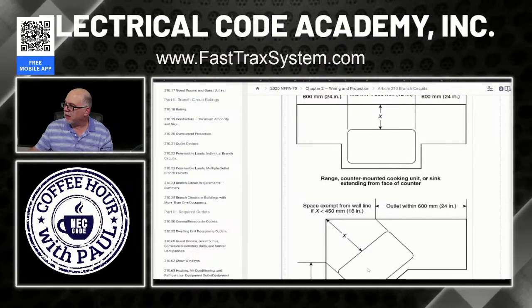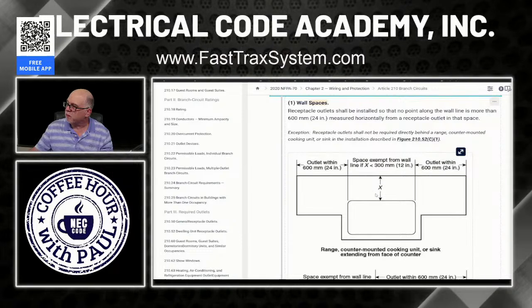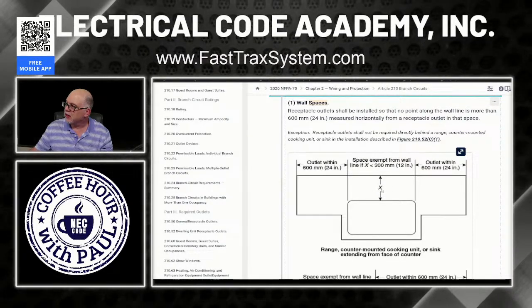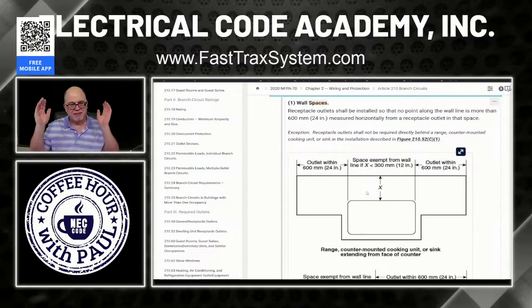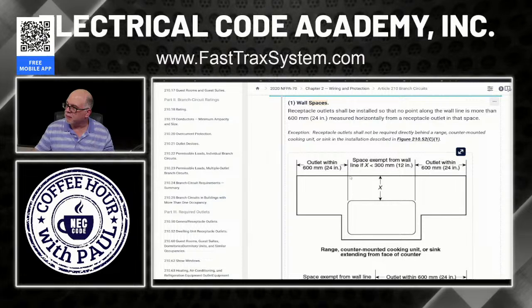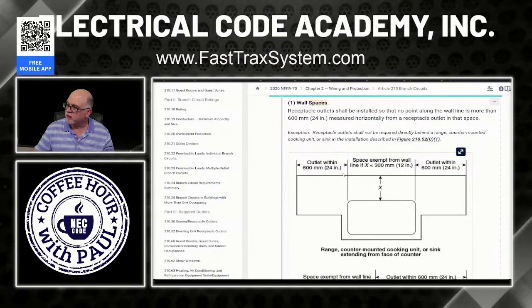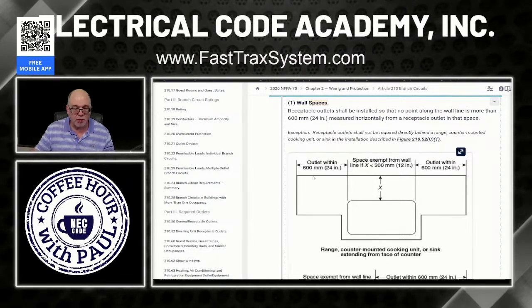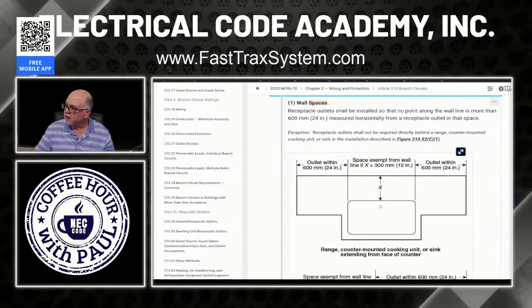All right. And so in this case, again, this space behind it, if X is less than 12 inches, ignore it. And the measurement starts here. Imaginary line comes back and you measure this way. And you have to have one within 2 feet of this imaginary line, which connects back to the wall. Perfectly fine. You don't have to count the space.